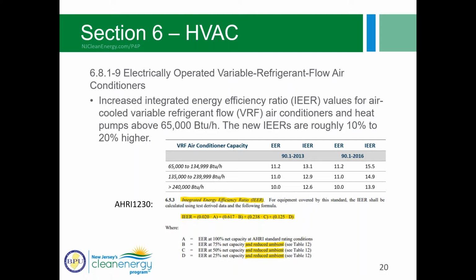And if you're not familiar with that, or even if you are, it's a rating that targets more what the actual operating efficiency of the unit is going to be. It weights operation at different percentages of time where it would be at reduced capacity and also reduced ambient. The reduced ambient condition is the larger driver for improving the efficiency, because when it's a little cooler outside, the compressor doesn't have to work quite as hard, and so the system becomes more efficient. So the EER is the worst case design condition, where the IEER tries to account for how that efficiency improves during reduced ambient and part load conditions.